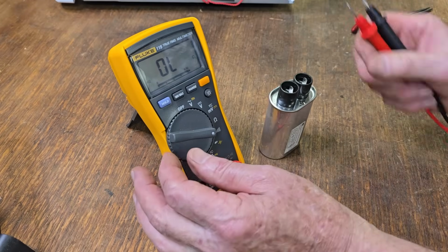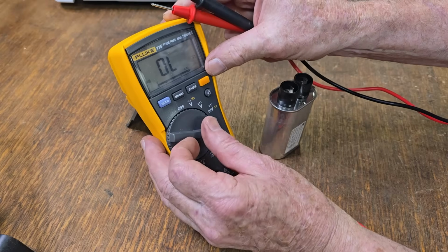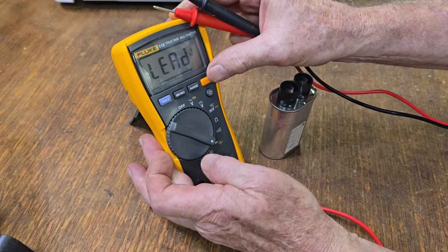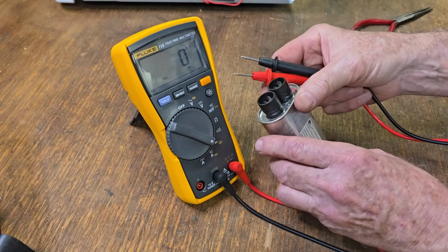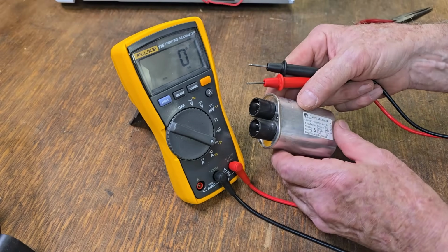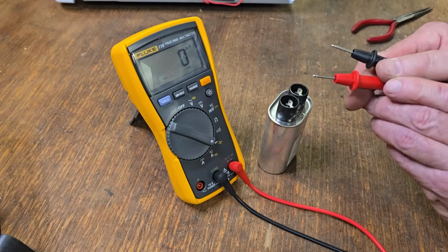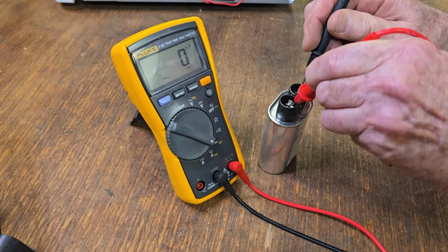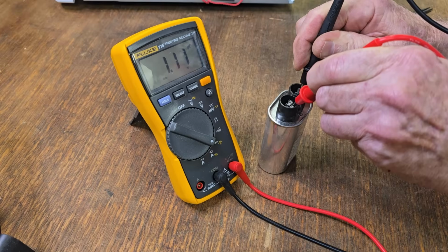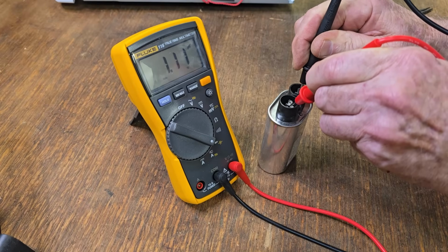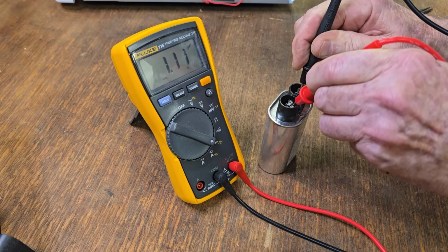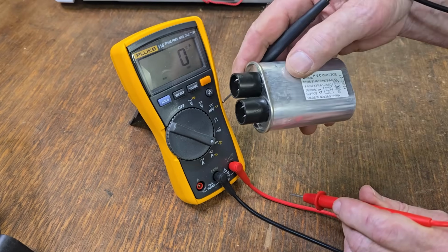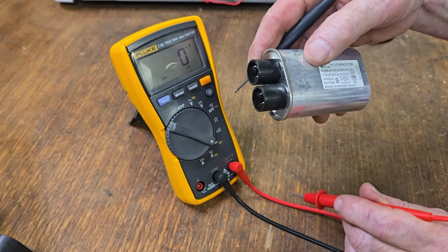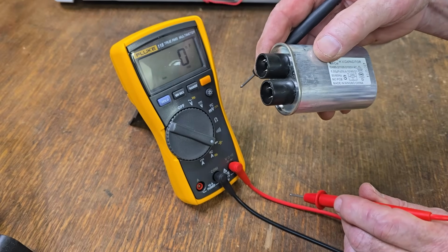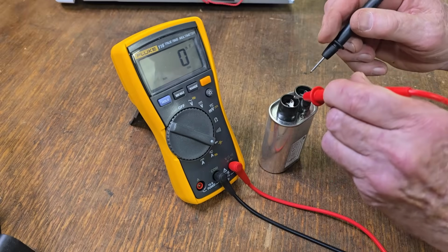We can now actually put it to our capacitance test. Remember, it says it should be 1.05 microfarad, so let's see what it gives us. We have 1.11, so that's pretty close. What was the tolerance? 3%. So 3% of 1 is 0.03.